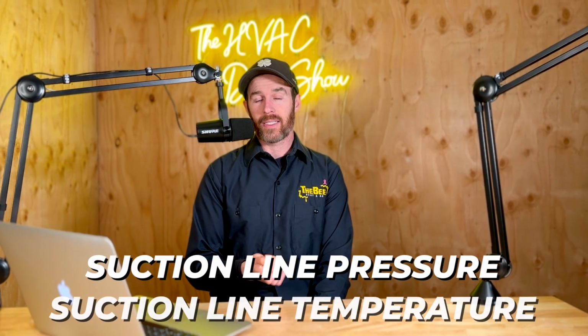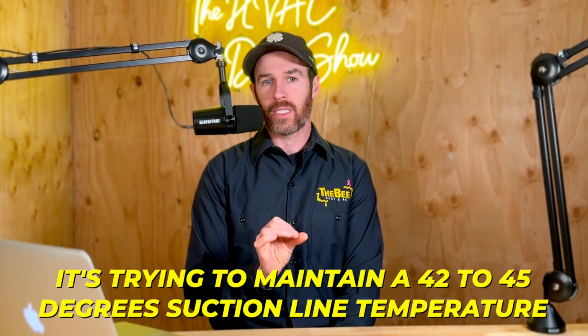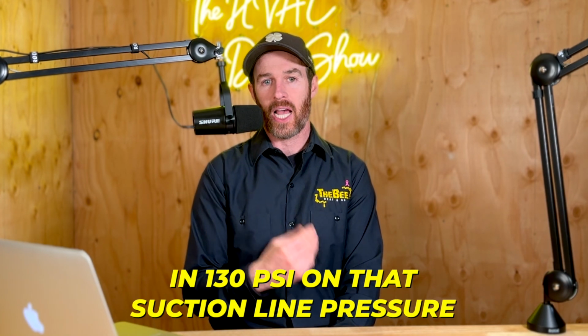This particular system functions a little differently than some other inverters, but they all work on similar principles, with temperature and pressure sensors throughout the system operating based on set points. This system is non-communicating, which has its own benefit I'll talk about in a second. It ramps up and down based on suction line pressure and suction line temperature, trying to maintain a 42 to 45 degree suction line temperature and 130 psi on that suction line pressure. On the liquid line, it's trying to maintain about 350 to 355 psi for head pressure.